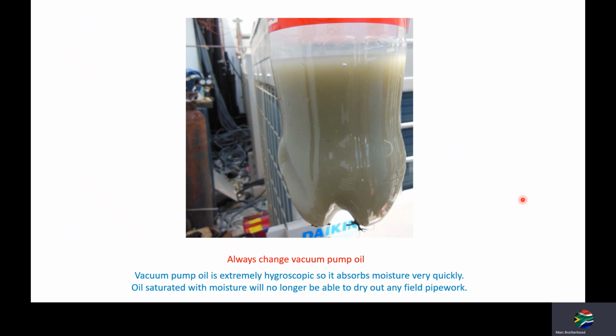It boils moisture. It lowers the atmospheric pressure in the pipework. And whatever moisture is in there, because of the low atmosphere, it's going to boil. And that boiling is going to be a vapor, and your oil absorbs the moisture, the vapor, and that causes it to go white. So you must always make sure you have new vacuum pump oil in.